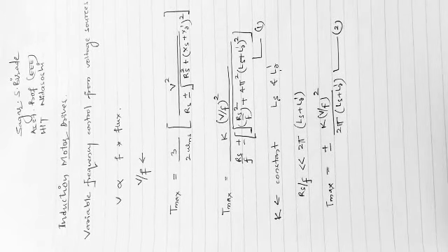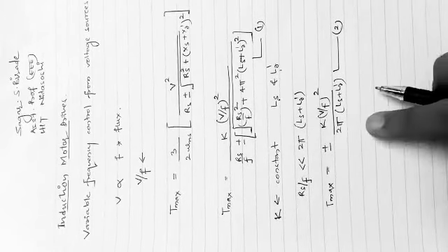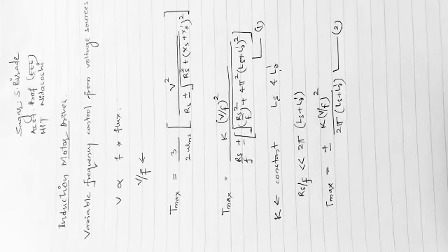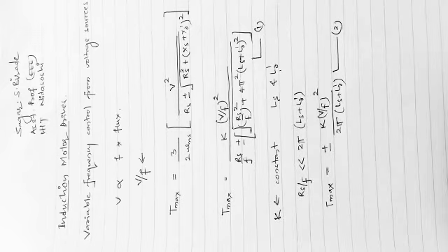Now when we go through equation 2, it suggests that if the V by F ratio is constant, then the motor develops a constant maximum torque, excepting at low speeds or low frequencies. Therefore, the motor operates in constant torque mode.